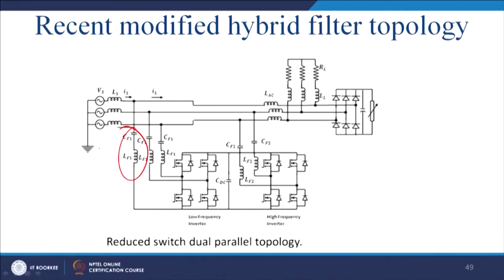And ultimately this has been tuned to the 5th and 7th harmonic with a Q factor of around 40, so that you can have a quite sharp resonance, and this has been tuned to the 11th and 13th harmonic. We do not leave anything for the passive filter, because there is an issue of detuning in the case of the passive filter, and in the hybrid filter also, because the passive part you were trusting will gradually decay.